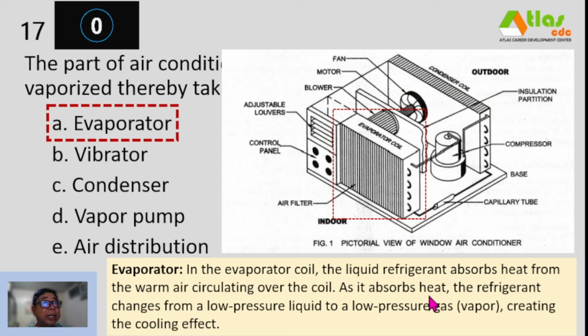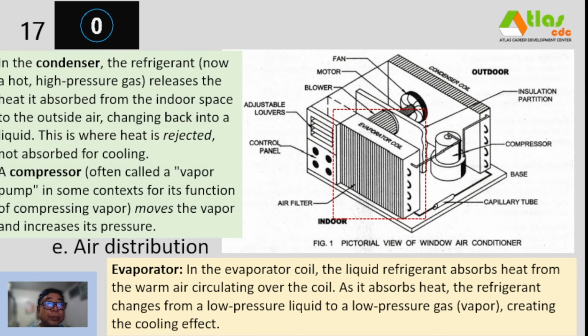No? And these are the other parts of the aircon unit. The compressor is here, and we have the capillary tube here, and we have the fan and the motor and the blower. So in the condenser, this one, the refrigerant now, a hot high pressure gas, releases the heat it absorbed from the indoor space to the outside air. Kaya dito lumalabas ang mainit na hangin, changing back into a liquid. So yung galing dito na malamig, no, sa compressor, pag umano doon, magiging liquid ulit, no. This is where heat is rejected and not absorbed for cooling. A compressor, often called a vapor pump in some contexts for its function of compressing vapor, moves the vapor and increases its pressure.